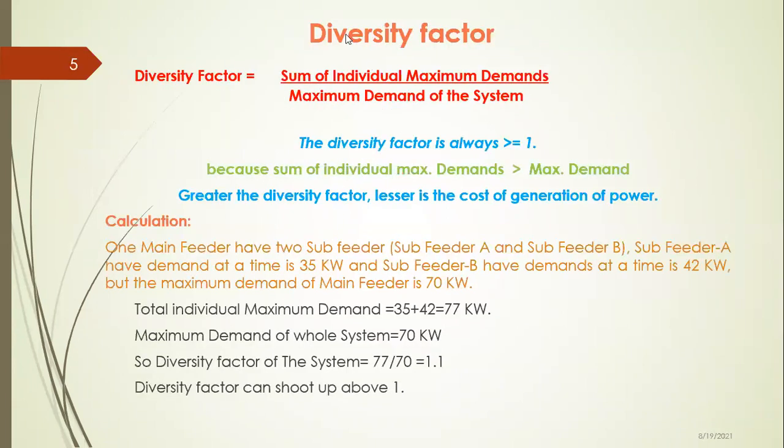Now the next is the diversity factor. Next definition, it is a diversity factor. So diversity factor is equal to the sum of individual maximum demands divided by the maximum demand of the system. And here you can take the example of your complete home.